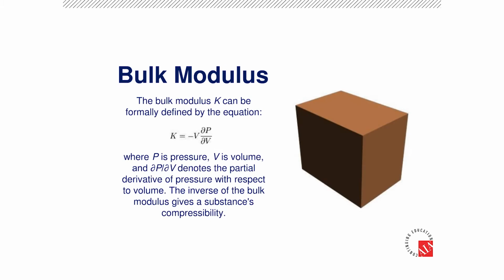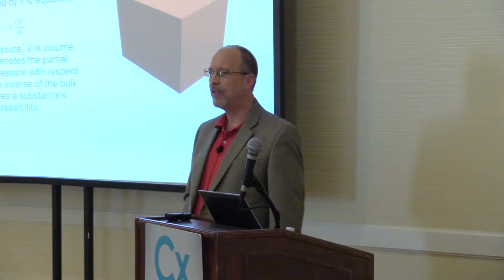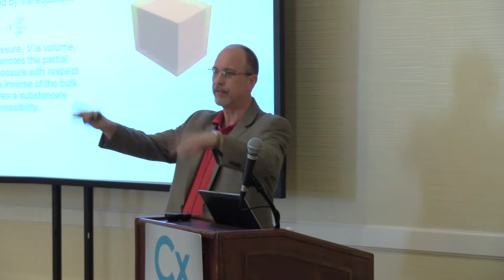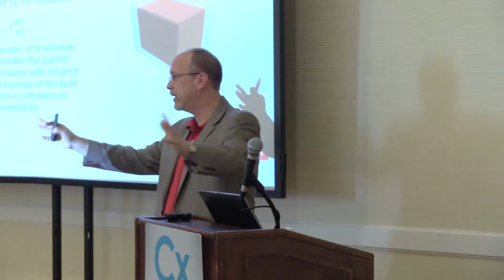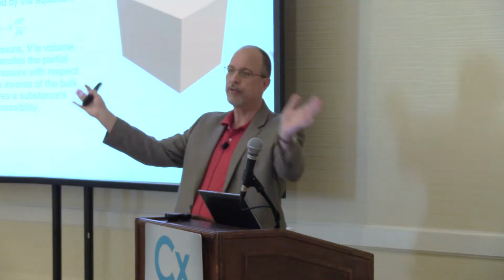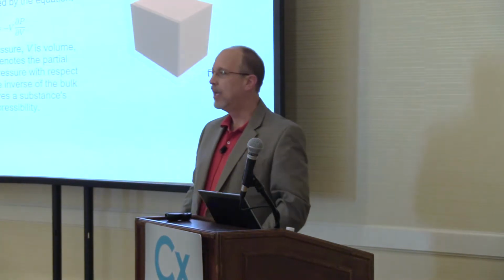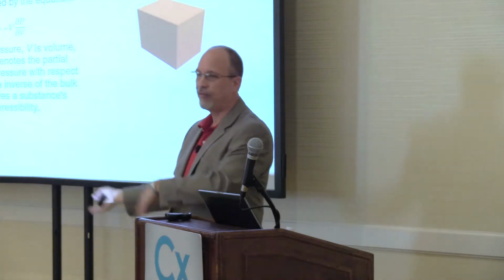Now, as part of the sound speed, we actually have to calculate out the bulk modulus. Liquid is compressible. So I've talked to you on the phone from time to time. I'll say, you really have a hard time zeroing the flow. Most of the newer flow meters, you don't need to zero. The ancient flow meters, you needed to zero. All the new flow meters, no zero. The factory zero is just fine. The reason being, they reach such low flows.